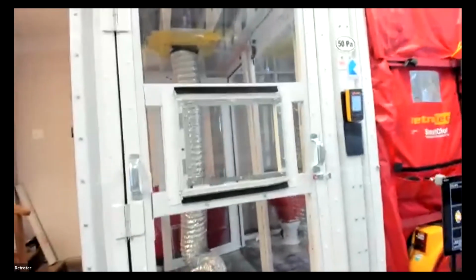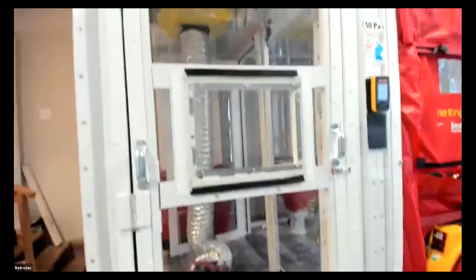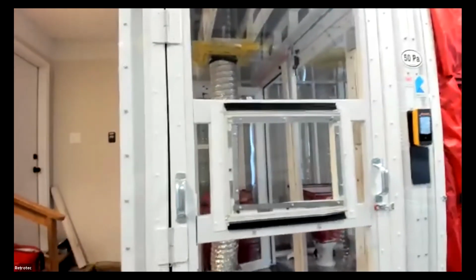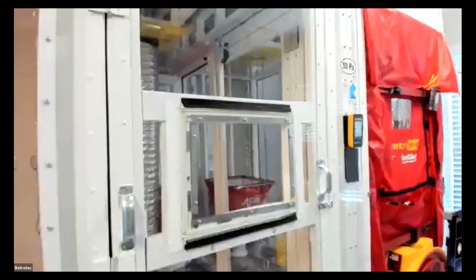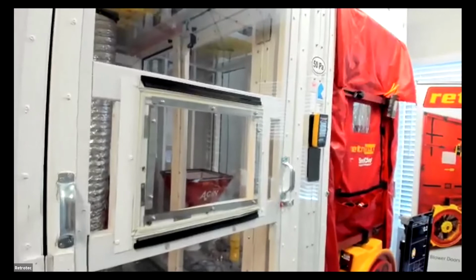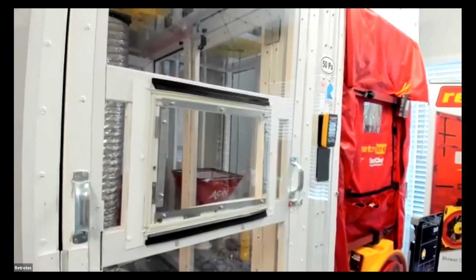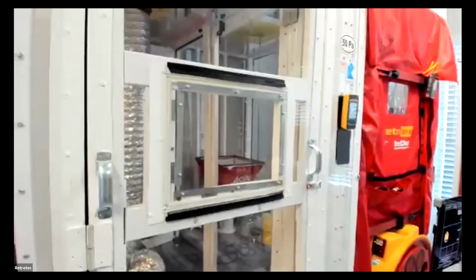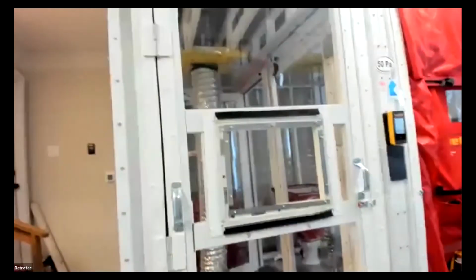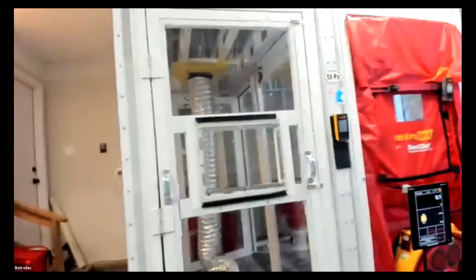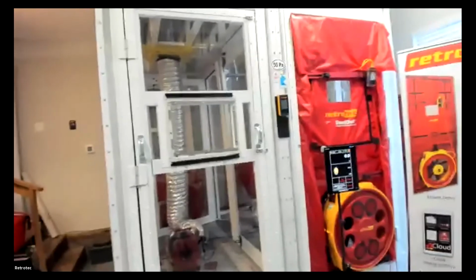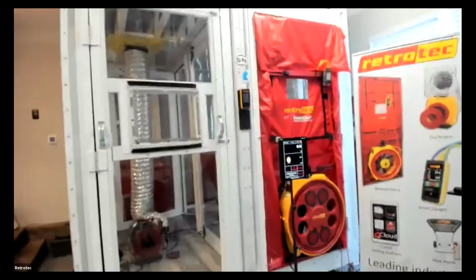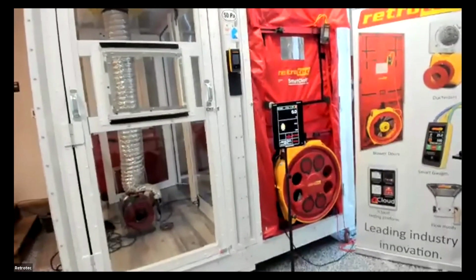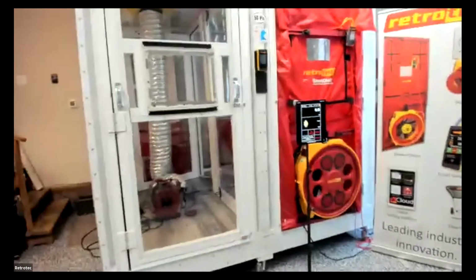So I'm going to see if I can get you guys closer just so you can get an idea of what's going on. You can see that we have this other duct tester here set up. We're saying that this is the return side, and behind there, you see some more tape, and that's going to serve as our supply side. And you see our blue tube coming down from there. So this chamber above is going to be our duct system that we're going to test. And then we have our blower door set up there for our duct leakage to the outside portion.